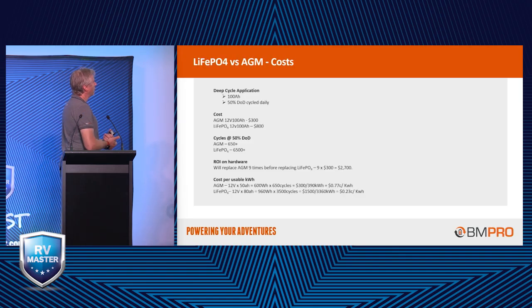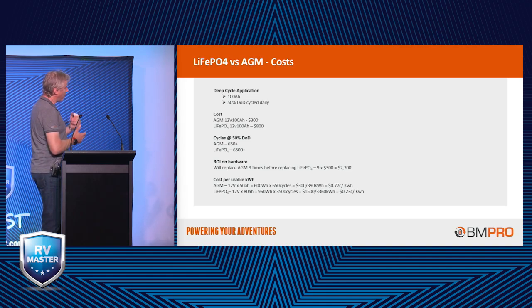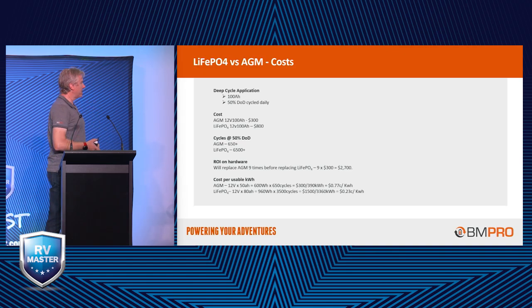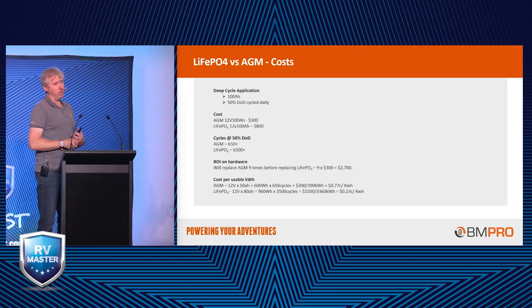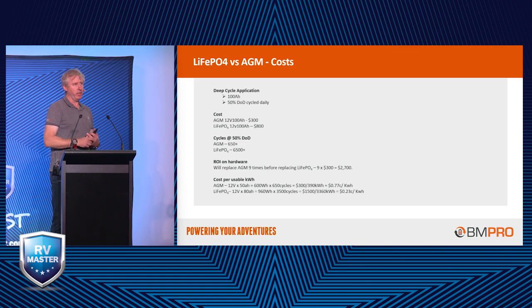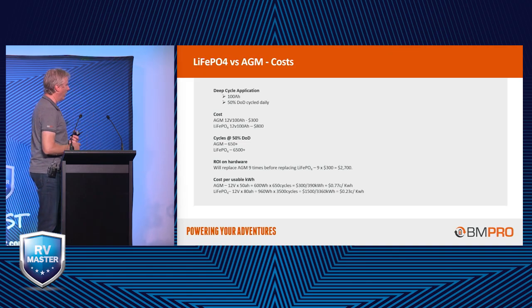Cost-wise, for deep cycle, let's do simple numbers—I had to adjust this down since lithium batteries are coming down in price. At 100 amp hours, 50% depth of discharge, a good quality AGM costs around $300, and a good lithium iron phosphate around $800. On an AGM, discharging down, you'll get maybe 650 uses. With lithium iron phosphate only going down 50%, you'll get over 6,000 uses—we got over 3,000 at 98% capacity, so well over that. That's why they say you can sometimes get up to 8 or 10,000 cycles. So for return on investment, according to those maths, you'd have to replace the AGM battery 9 times.